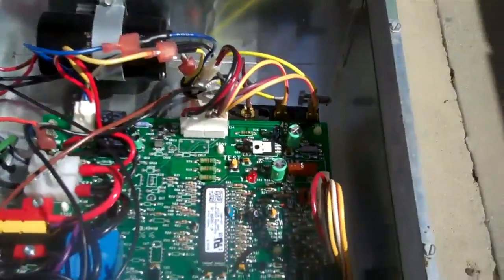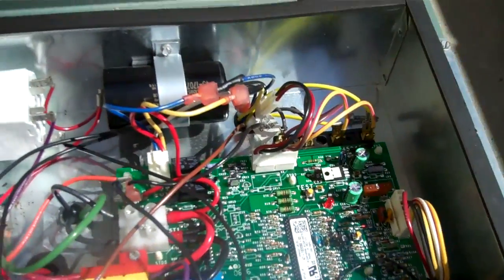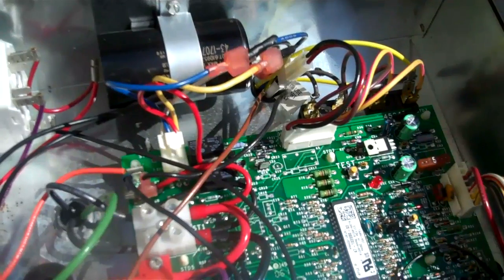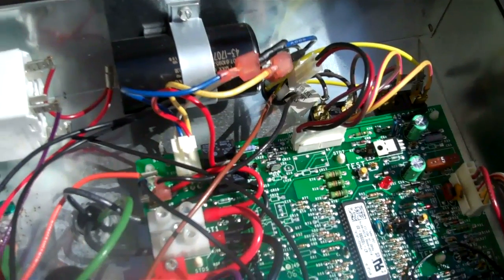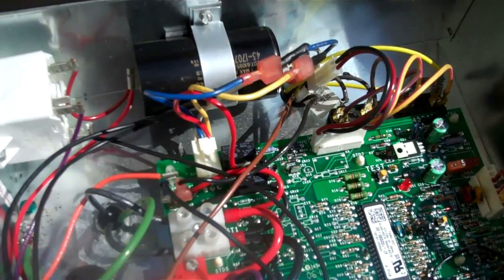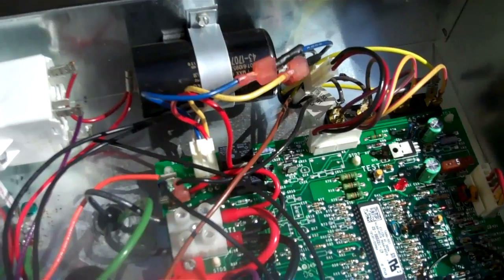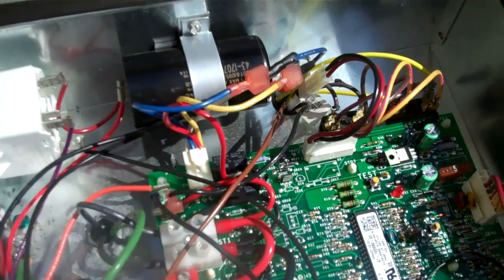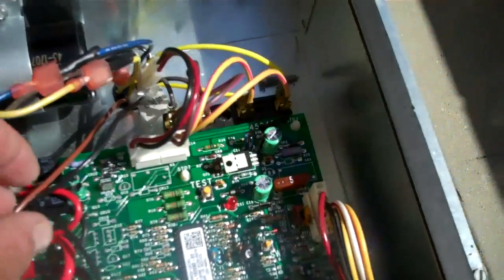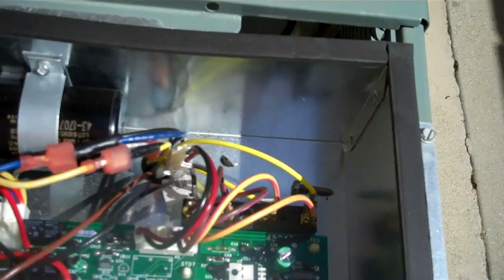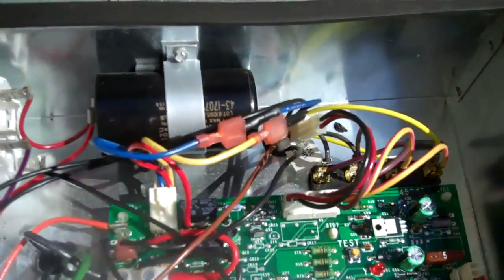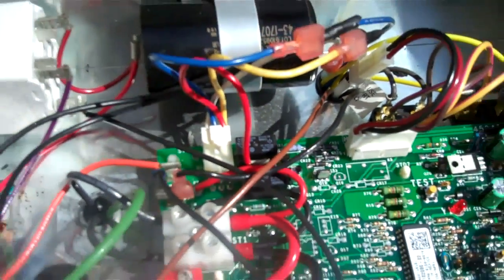So the control module here, these are the wires. The condenser fan motor has six wires. The black and the brown are the 230 volts and it goes into a plug. This plug is all 24 volt wires for the two speeds and how it ramps from first and second stage.